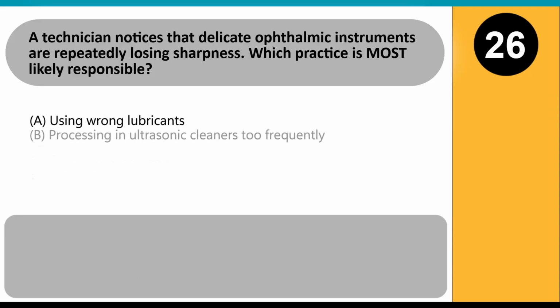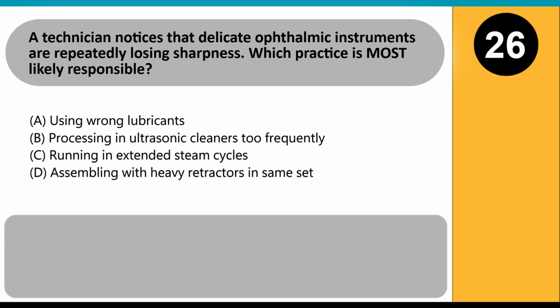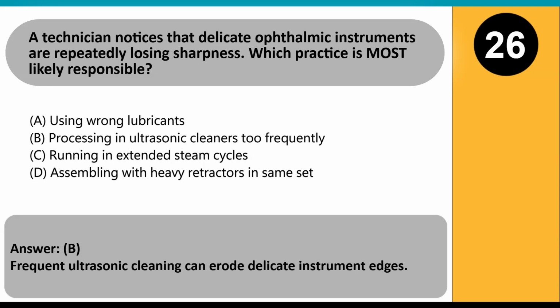A technician notices that delicate ophthalmic instruments are repeatedly losing sharpness. Which practice is most likely responsible? A. Using wrong lubricants. B. Processing in ultrasonic cleaners too frequently. C. Running in extended steam cycles. D. Assembling with heavy retractors in same set. Answer: B. Frequent ultrasonic cleaning can erode delicate instrument edges.